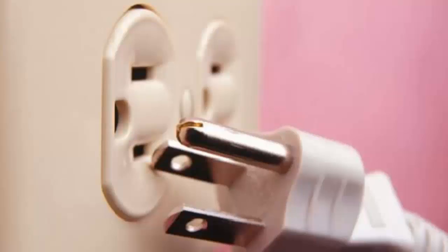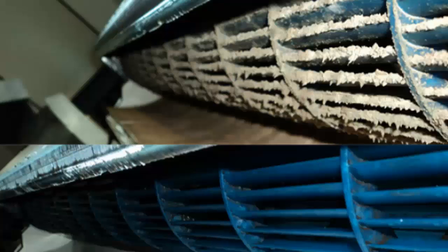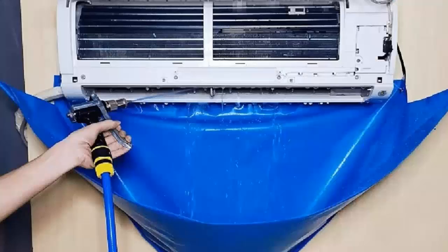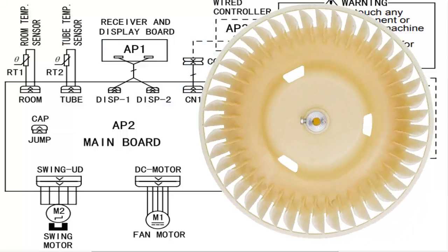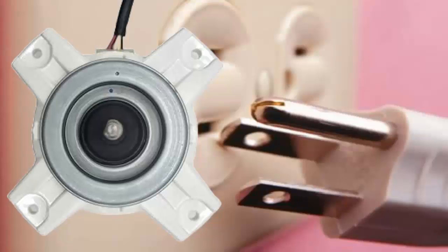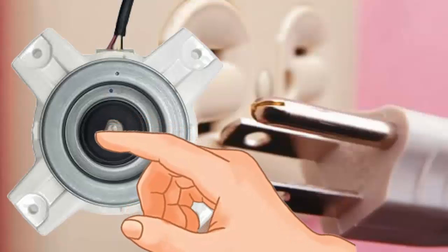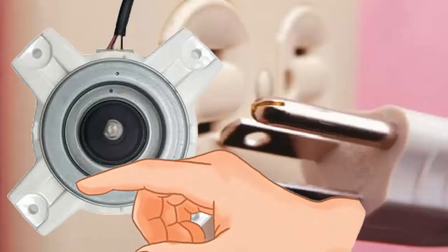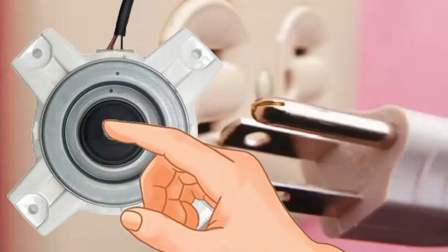3. If the fan motor is dirty, it may not be able to spin properly. 4. If the power cable is loose or damaged, it should be repaired or replaced. If the electrical connections are faulty, they should be cleaned or repaired. 5. If, with the equipment turned off, the fan cannot be freely rotated by hand without noise, the fault may be located in the fan bearings.